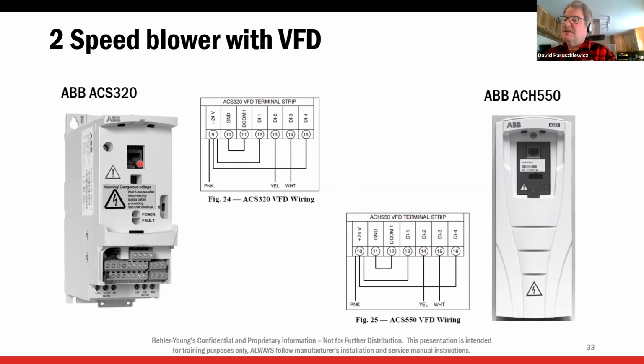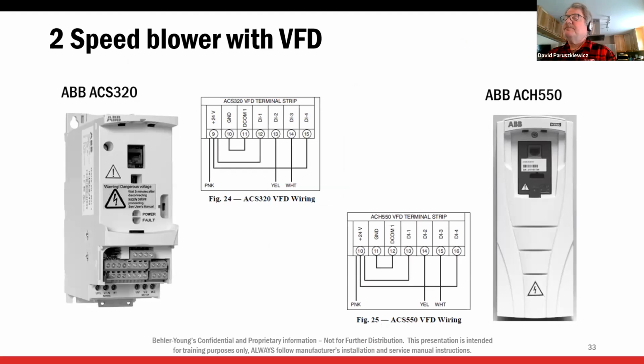So how would I troubleshoot this? Well, my blower's not running. All right, so first of all, do I have incoming line power? Yes. Do I have outgoing line power? No. Do I have a fault light? No. So let's check for voltage. So again, when this 24 volts DC comes to this input or this input, it's going to turn the blower on. So let's take my DC voltmeter, check from here to here. Do I have voltage?